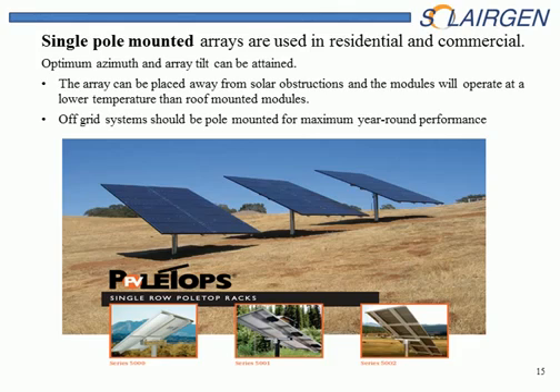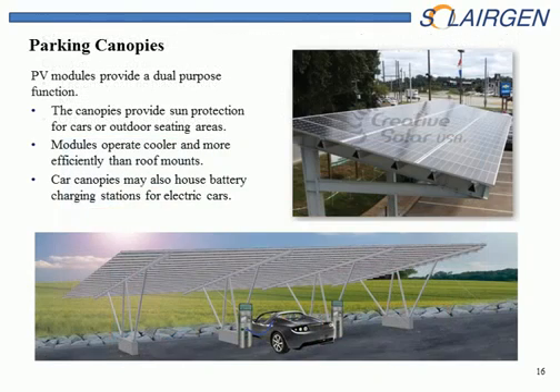Single pole mounts are common with commercial and residential installations. This type of mount is away from the structure, so it really doesn't pose any kind of a hazard for a first responder. Parking canopies or canopies next to the roof are very common these days. So you may see a canopy that's actually attached to a structure, or you may see the canopy that's separate. If it's separate, it really poses no hazard. All the DC and AC are separate from the building. If it's attached to the building, then treat it as if it were on the building itself.